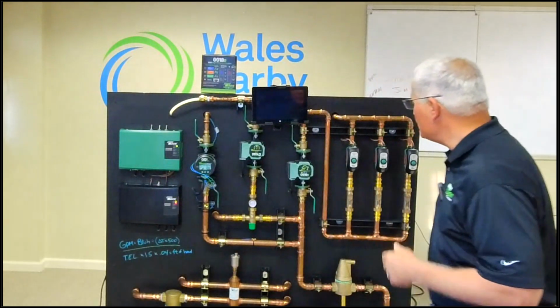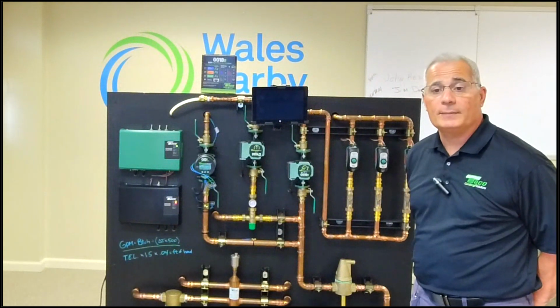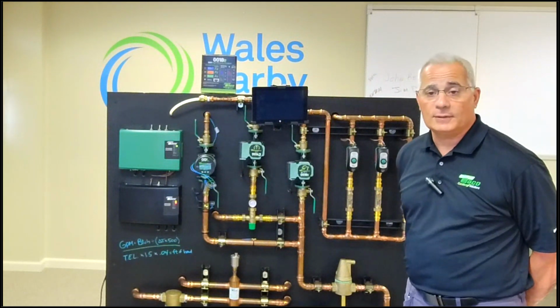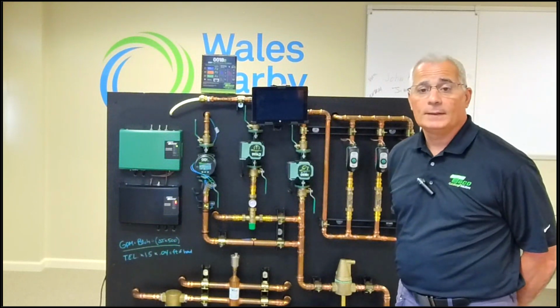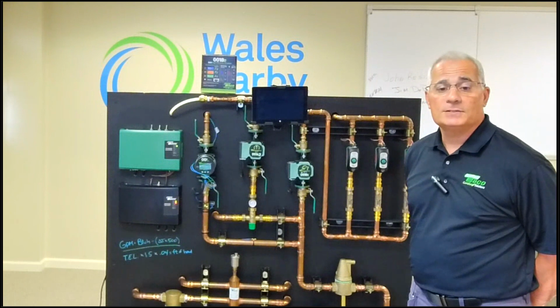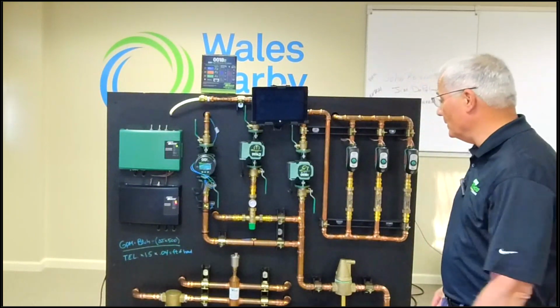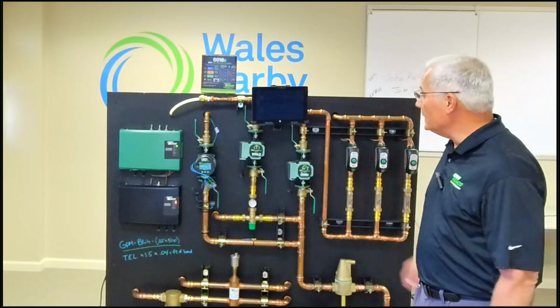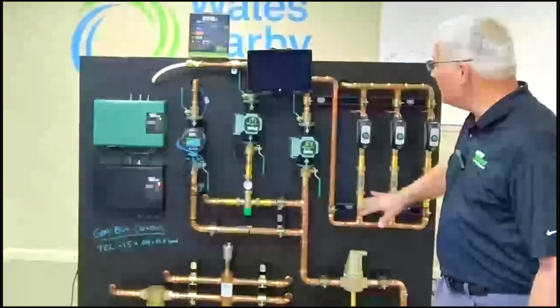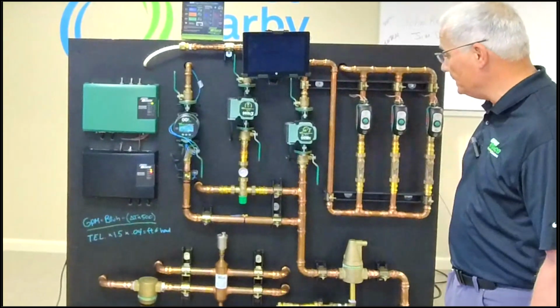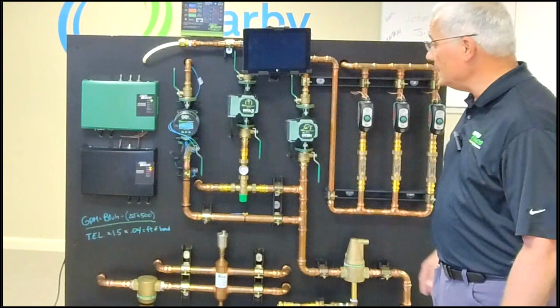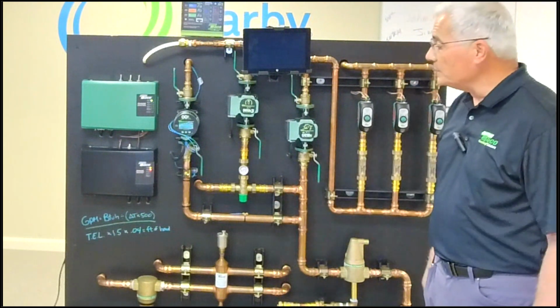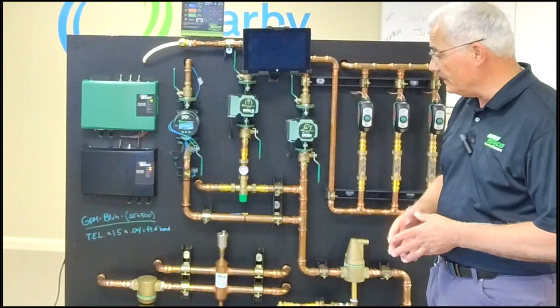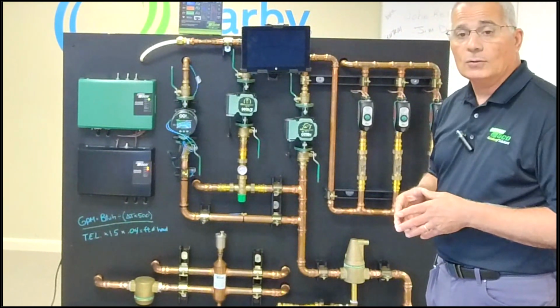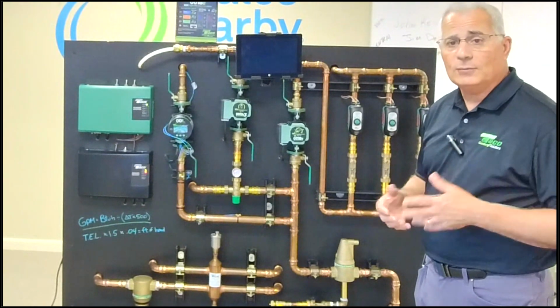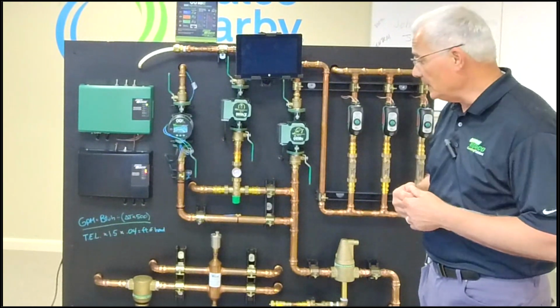So we have this live fire display. One of the things that we've been trying to do for this webinar season is have more live interaction webinars. So this is not going to be any PowerPoint. This is just live stuff, so you're going to see it happening as we switch things on and off. We have two different scenarios here. We have a typical cast iron piping setup with a 3-zone system and a zone of radiant. And then we have another scenario where we would be switching over to a condensing boiler system, and there I would have a low loss header or closely spaced tees. Quick review on piping to make sure everybody's up to speed and understands what we're talking about.